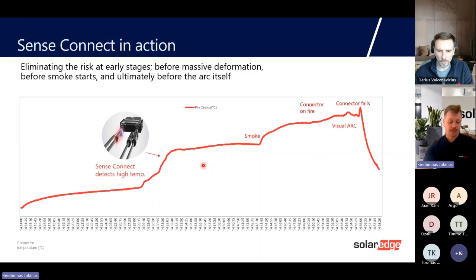So for that reason, we understood that one of the weakest points on the roof is MC4 connectors. You have hundreds, thousands of MC4 connectors, depending on the size of the installation. Even in a small installation, you can have 20, 30, 40 MC4 connectors. And if they are not connected well, if you didn't press enough, if you didn't use the proper tools, or even if there is a manufacturing error, it happens. Yesterday we had the same webinar for the Lithuanian audience, and they said, yeah, we've seen burned MC4 connectors even from PV manufacturers when connecting PV modules in series without using optimizers. So here SolarEdge realized that this is the weakest point. A study says approximately 70% of all failures come from the MC4 connector.